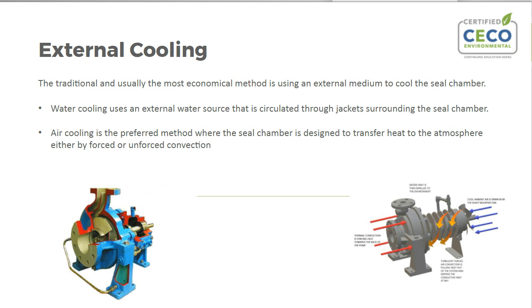In order to protect that seal, for years we used external methods to protect those seals, and still do today. Those methods started out using cooling water, an external water source coming in. So this had nothing to do with the pumpage, nothing to do with what you were pumping. You would pump this cooling water through jackets that surround the seal chamber, basically cooling that seal chamber down, cooling the seal down, regardless of what temperature you were pumping up in the business end of the pump itself, where the impeller and casing are. So it was cooling just a localized area of the pump.